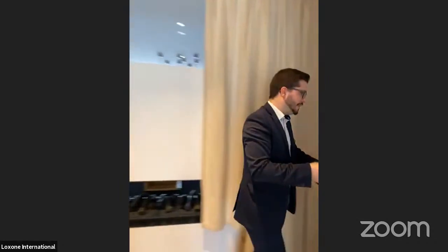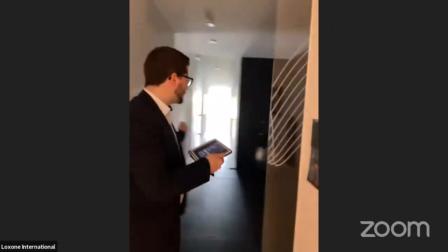I think we should go down to the technical room, shall we? I think the time is right. So follow me downstairs, and meanwhile I will talk about the difference between motion and presence. That's a good question. Motion is if you move: there is an optical infrared sensor, and if you move, it gets you. If you stay still or sit down, watch a movie, or type something on a keyboard, you might not be seen. Presence is something on top of it. In our presence detector there is also an acoustic sensor inside, which detects if something in a room is loud. If you watch TV or type something, it might be enough that the presence sensor will still detect you. So it's more accurate in a way. Okay, so let's go to the technical room now.